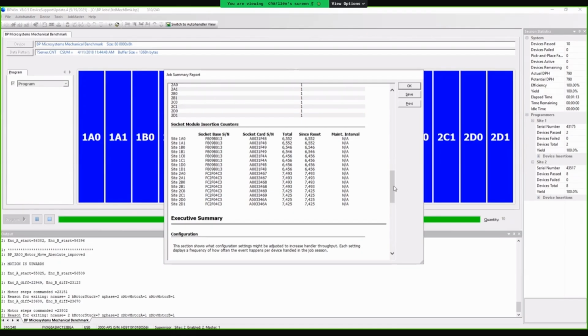We ship a diag card with the machine to perform a diagnostics test as well. We do have a diagnostic card that will test everything up to the socket connections on the programming site, checking all analog digital pins, all timings, all voltages, making sure that everything is within specifications. Anything that deviates will be marked as an error and the diagnostic will fail.